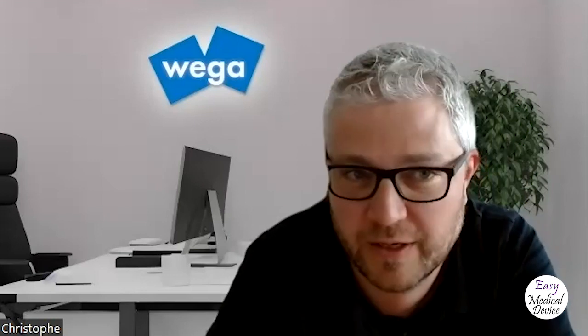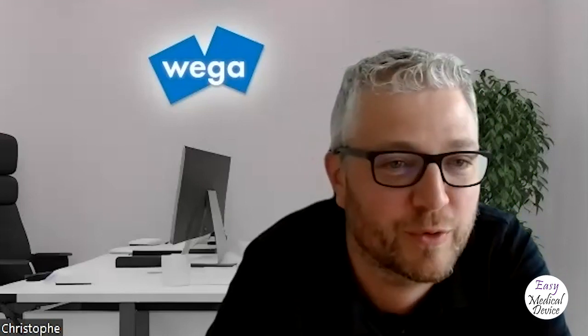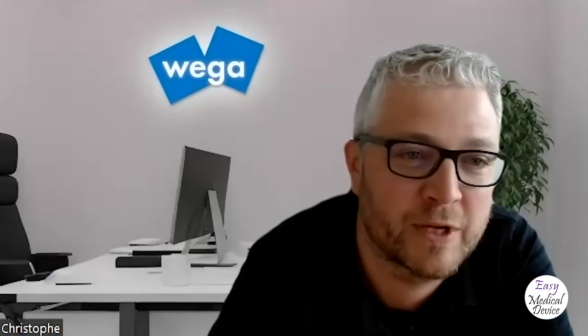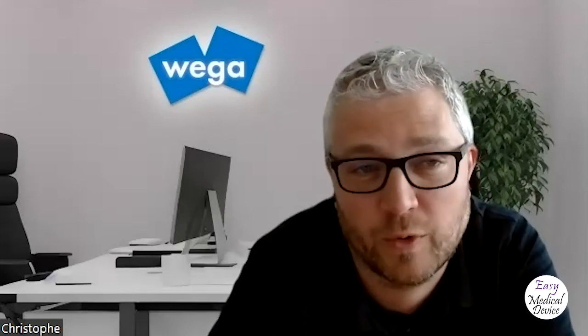Yeah, that's a frequent mistake, but in our volatile world today, that is not really possible. You don't just put one software version in place and forget about it for the rest of its life. Normally, you will perform some changes or modifications. You might purchase a new version of the software. So each time you need to recheck what the changes are, how they impact the data I already have, which new functions are there, and how I need to mitigate potential risk with those new functions. Where it becomes really more tricky is that many customers use software as a service.